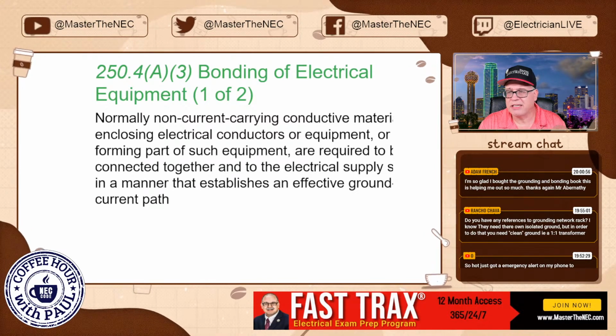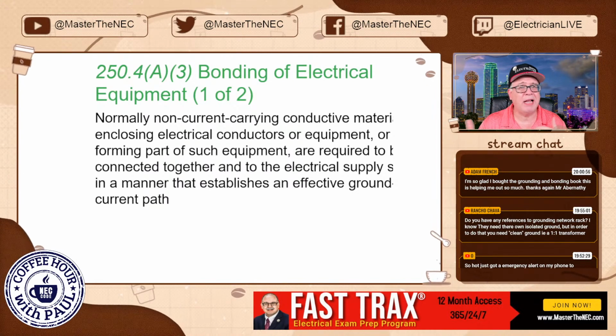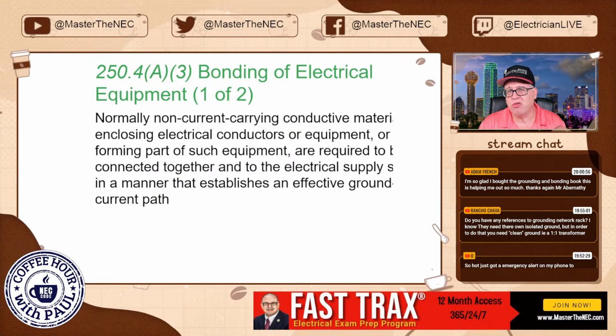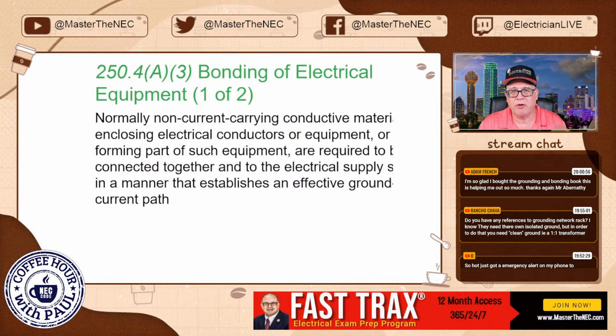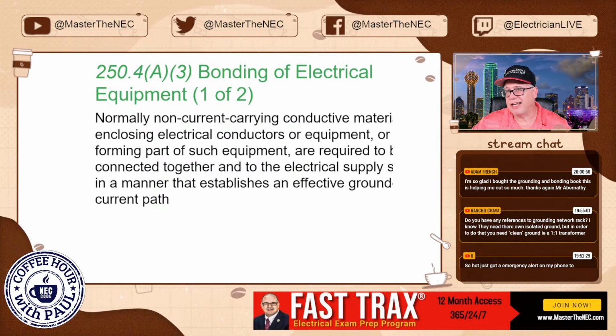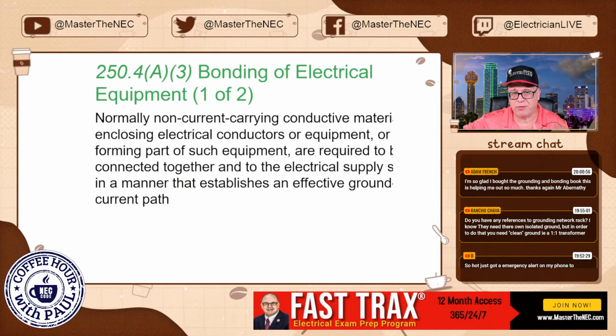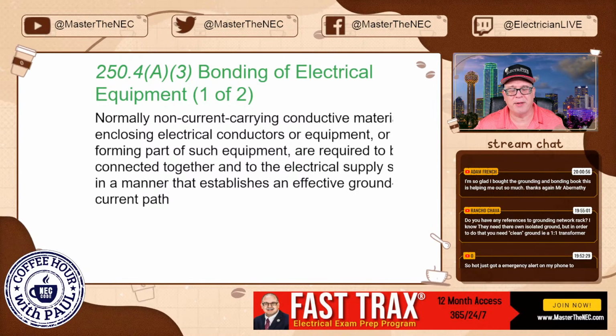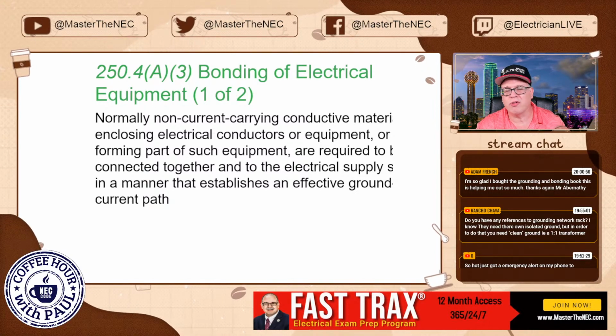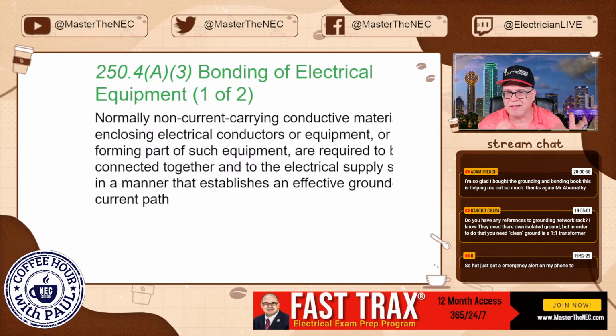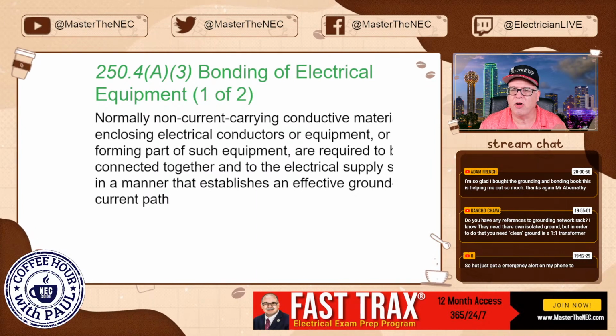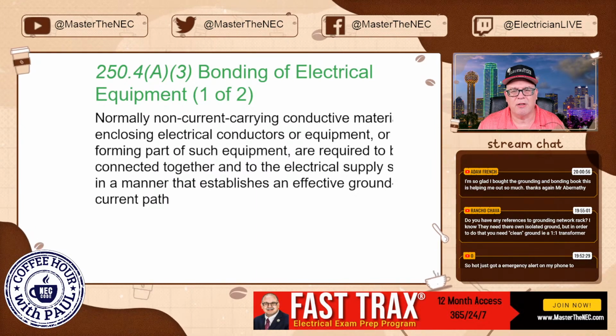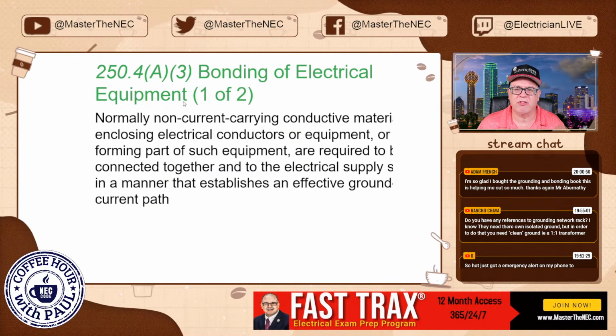Reliability, clearing that overcurrent device, or at least bonding the components together to reduce touch potentials on certain things. As you start getting further down the system, the touch potential concern goes away a little bit, but the closer you are to the equipment, switchgear, things like that, it's just vital that you make sure all these connections are adequate.